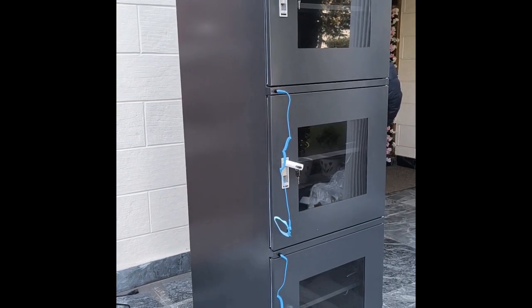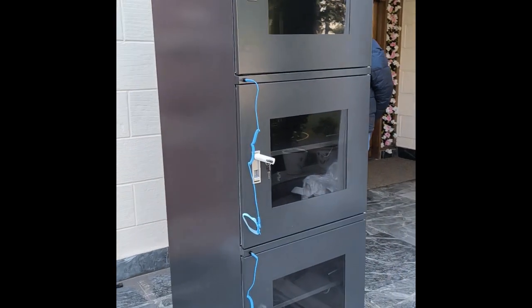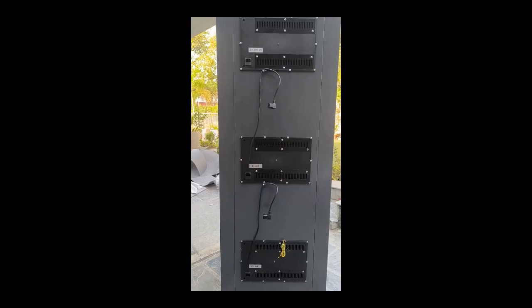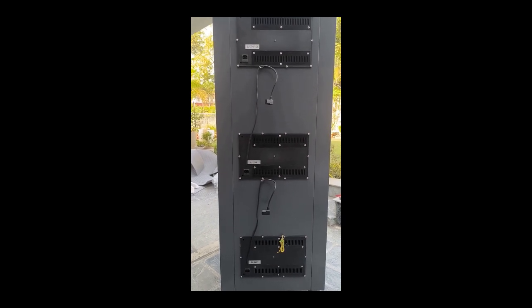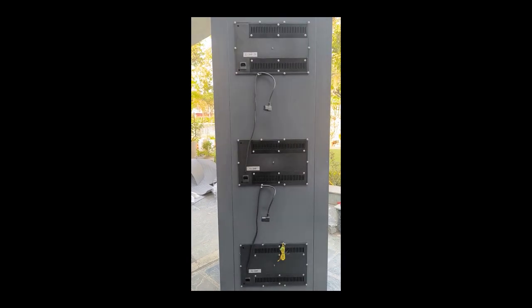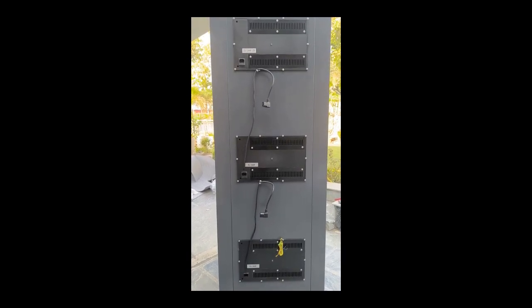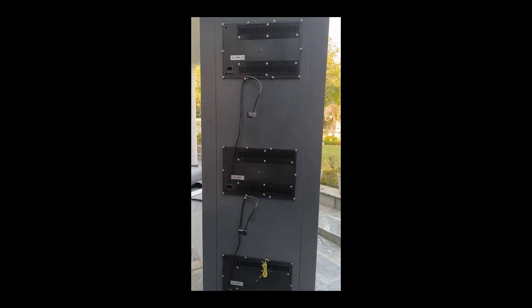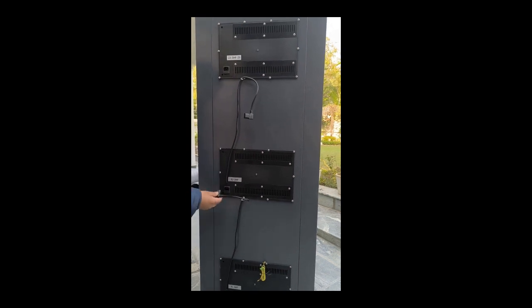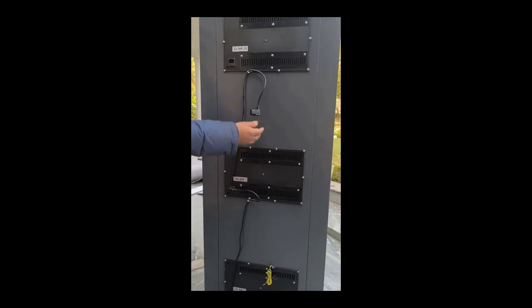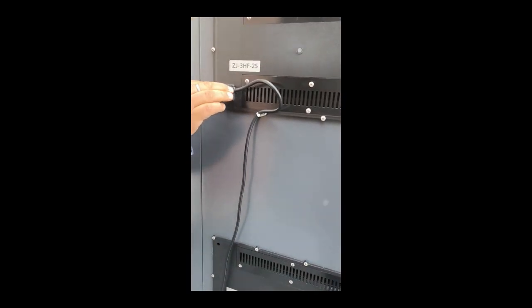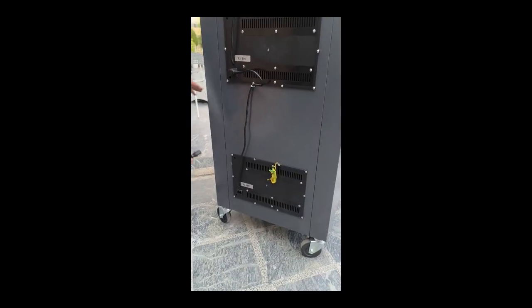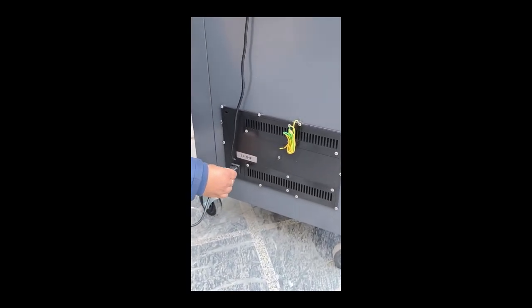Next, we will explain the connection of the main power source to the dry cabinet. On the rear side there are three desiccators. These three desiccators should be connected to the external power source with the help of connecting cords. Use the interconnection wire to connect these desiccators, which are interconnected in parallel. The external power cord supplied along with this dry cabinet should be connected to the third desiccator mounted on the bottom. Now the interconnection of these three desiccators with the external power source is complete.